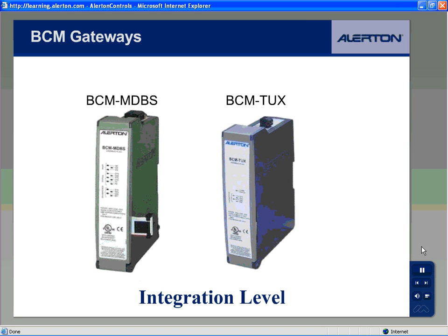The BCM MDBS Modbus is a BACnet compliant gateway to a Modbus network. Modbus is a serial communications protocol used for process control with industrial programmable logic controllers. The BCM MDBS is a fully programmable network controller that hosts its own schedules, trend logs, alarms, and DDC.